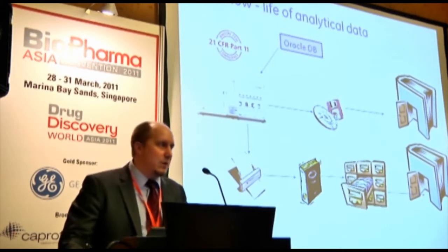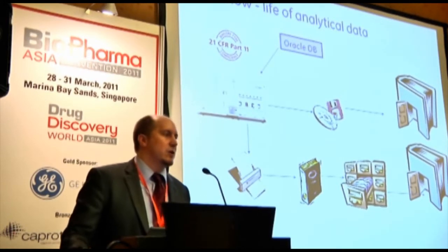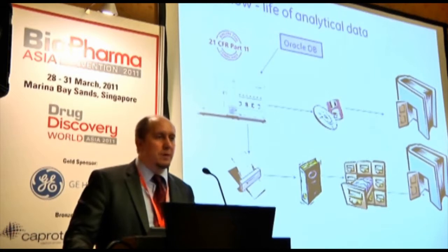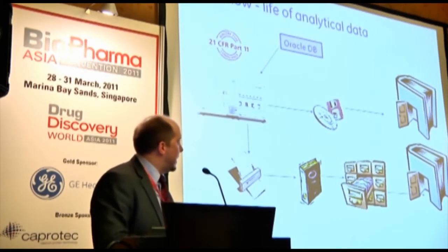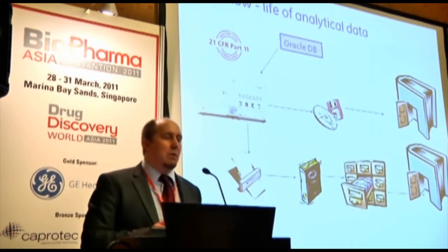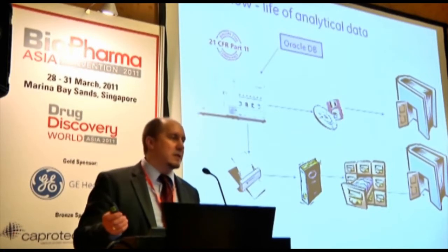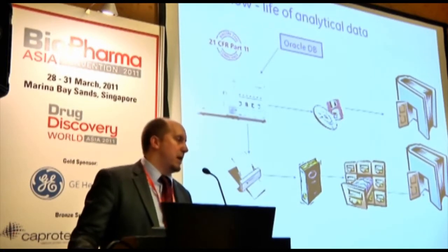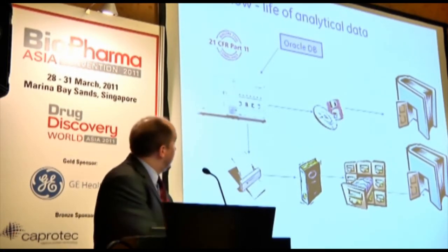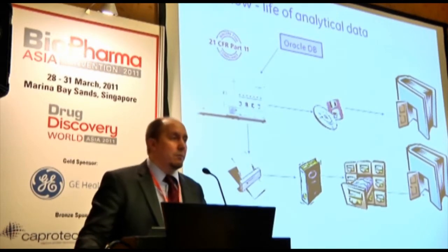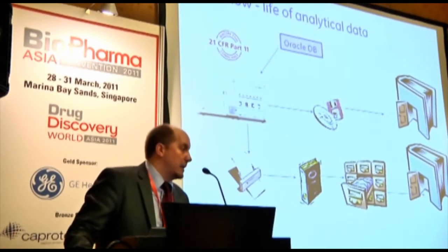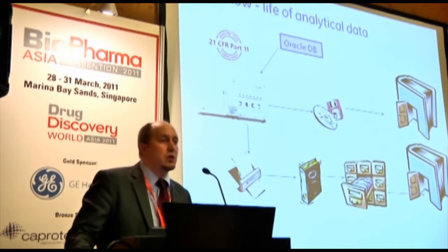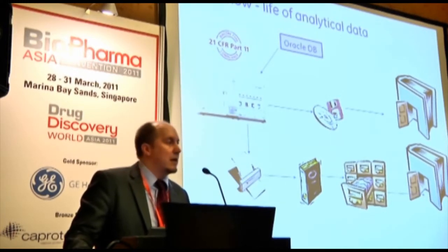In order to do that, we have implemented in our systems a database, an Oracle-based system, to manage and sort the data and to enable import and export of data in a seamless manner to laboratory information management systems, all done under 21 CFR Part 11 compliance, which is of additional interest because these types of requirements are also getting highlighted by authorities.